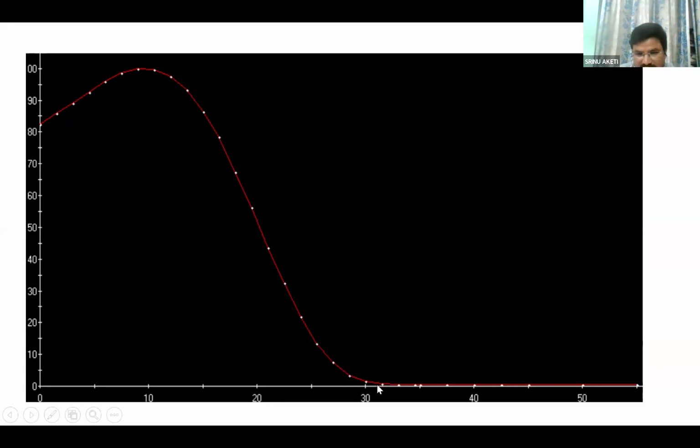That is the dose, this one. The X-rays will travel further, right? Yes, sir. That means X-ray contamination in the electron beam. How did you get the X-rays? From the target, when the electrons are coming, they hit different materials in the head, like the X jaw, Y jaw, MLC. When they hit those, they will emit X-rays. That is the X-ray contamination dose, the Bremsstrahlung dose.